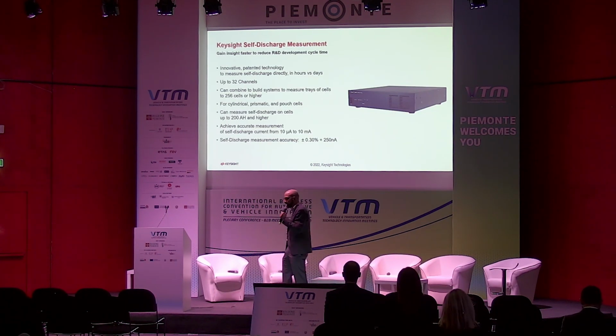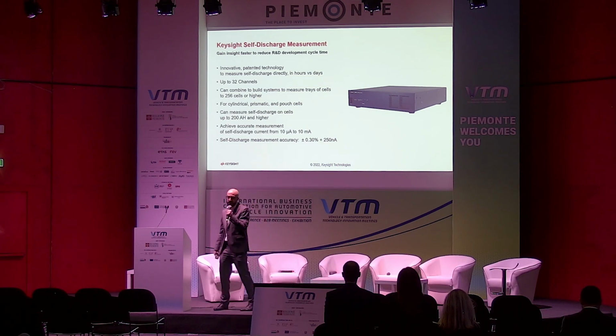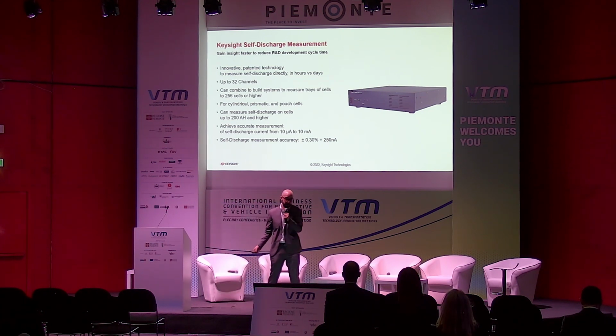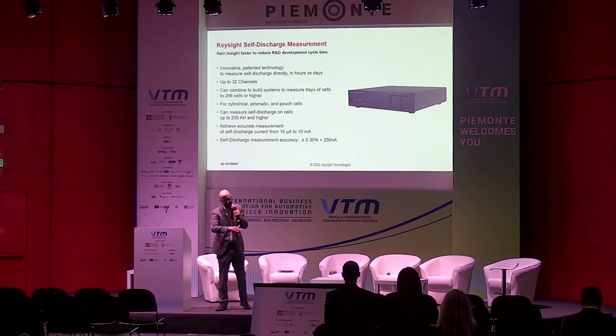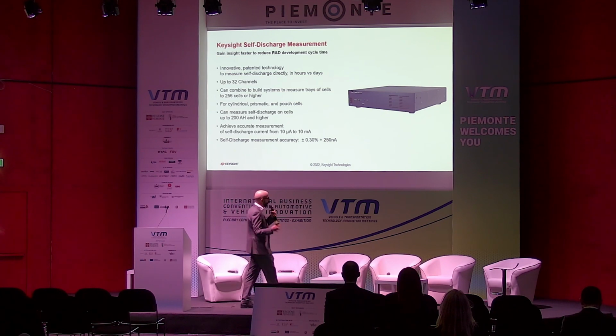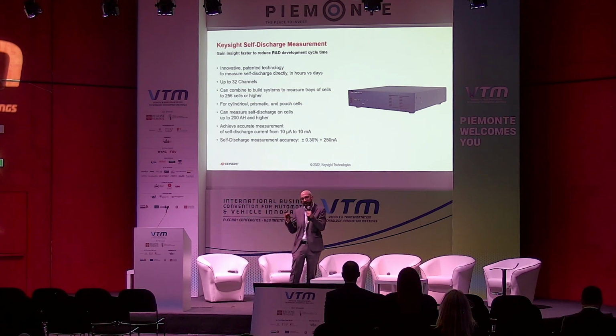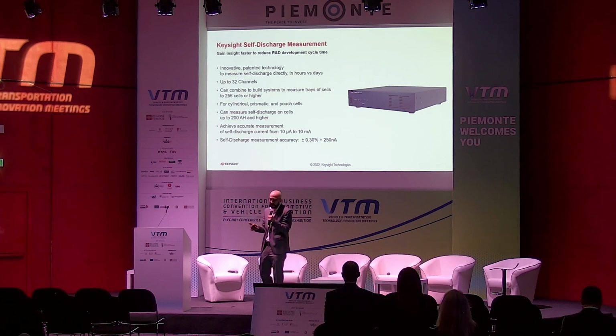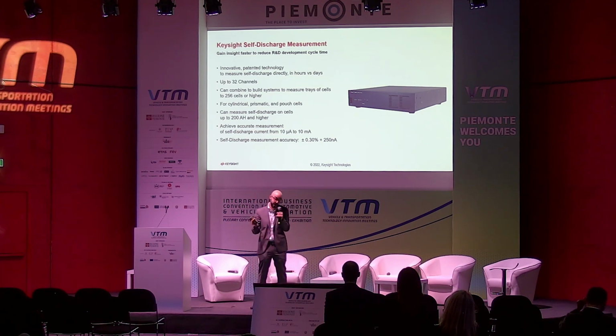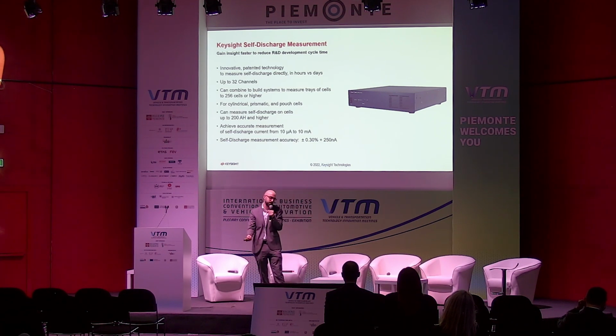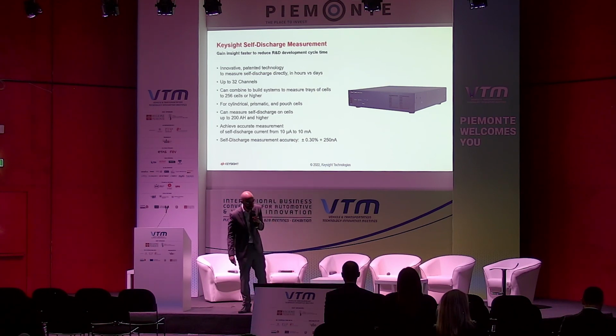Okay, let's come to the product. This is the Keysight product, which is able to measure the self-discharge using the potentiostatic method. Again, it's an innovative technology, and it's being patented by us, and it can go up to 32 channels. But of course, you can also place multiple of these systems in parallel to achieve more channels. Again, for measuring this kind of leakage current, you need really high accuracy, and we can achieve the measurement from 10 microamps to 10 milliamps, and the accuracy is 0.3% plus 250 nanoamps.